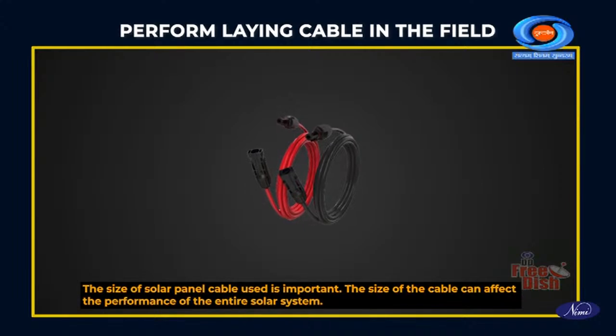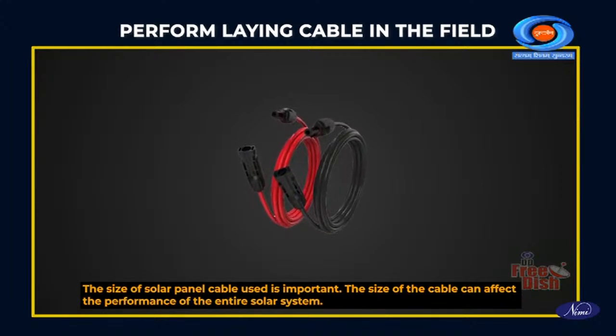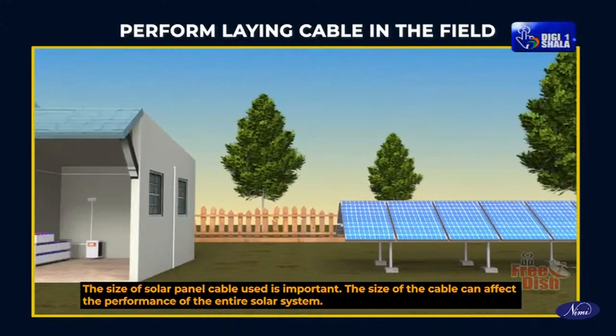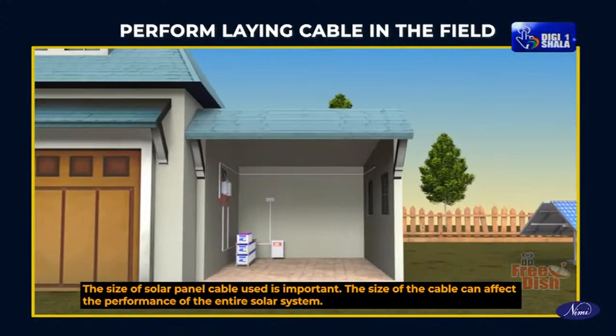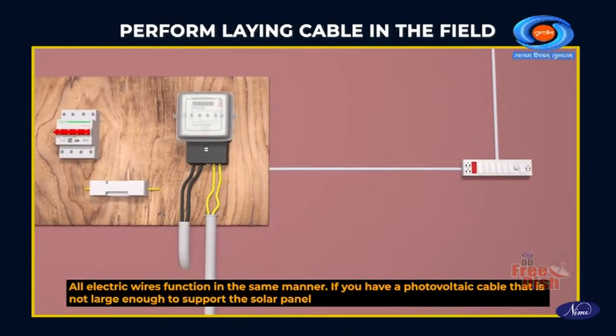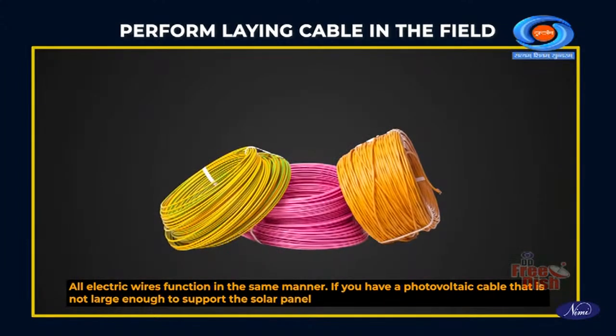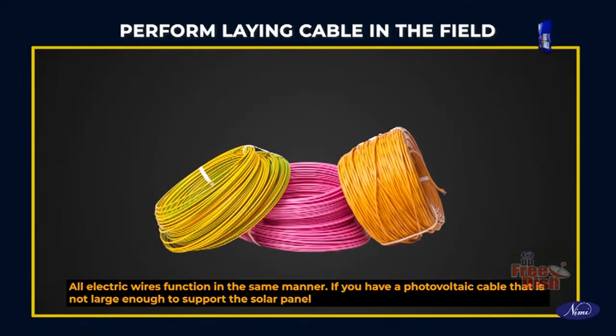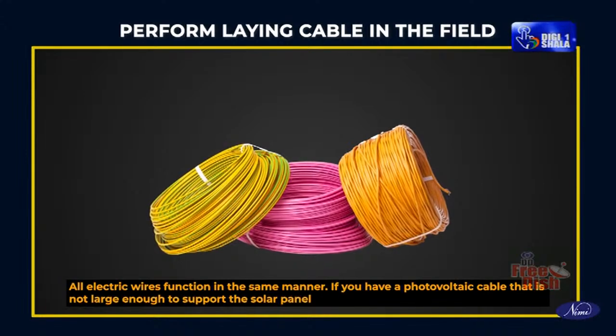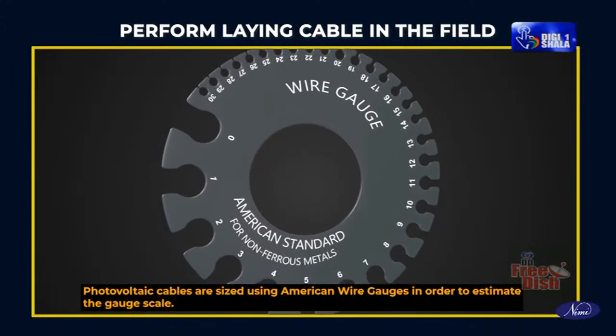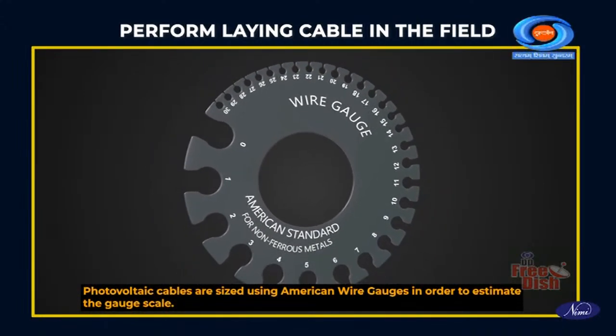The size of solar panel cable used is important. The size of cable can affect the performance of the entire solar system. All electric wires function in the same manner. If you have a photovoltaic cable that is not large enough to support the solar panel, it can cause problems. Photovoltaic cables are sized using American wire gauge in order to estimate the gauge scale.